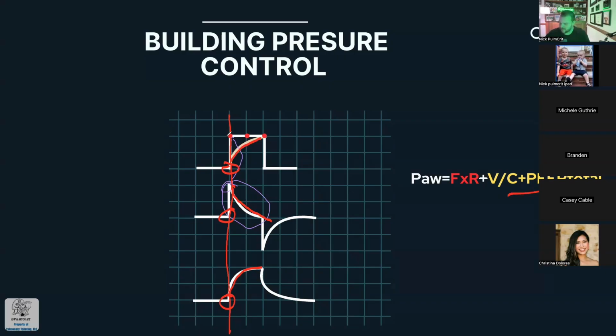But if you have someone that's participating in breathing, breathing spontaneously, they can choose to drop their diaphragm and add more pressure from below. So the vent's pushing and then the patient's pulling. And remember, flow is unfixed. Because flow is unfixed, they can pull more flow and volume than their lung mechanics allow. So this flow curve gets kicked out, right? The flow curve gets kicked out.